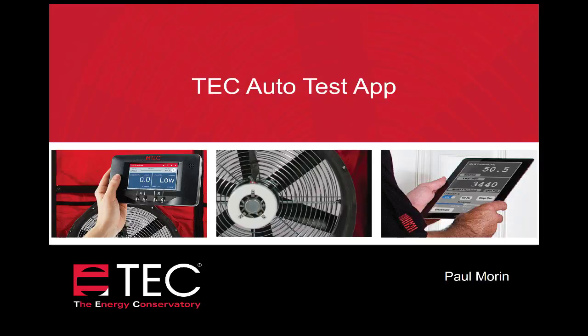Today we're going to be introducing the TEC Auto Test app. This webinar will introduce you to our newest app that will allow you to do an automated blower door and duct leakage test from an iPad or an iPhone. The auto test app will generate a report with data directly from the DG700 with a Wi-Fi link or from a DG1000. And a PDF report will include your location, a geotag, and the time of test, the timestamp.